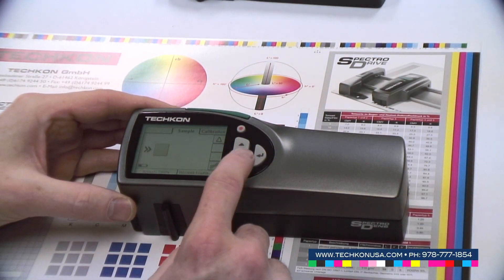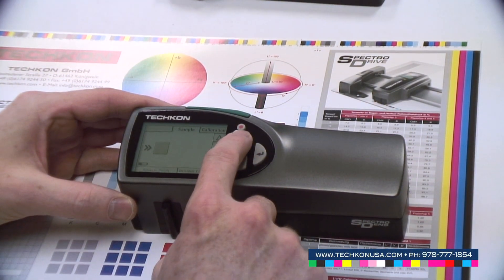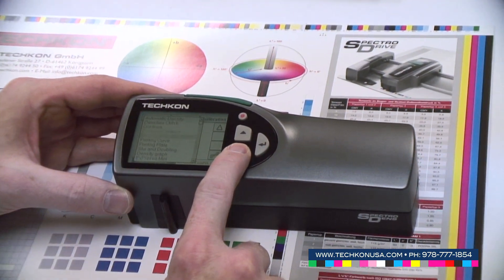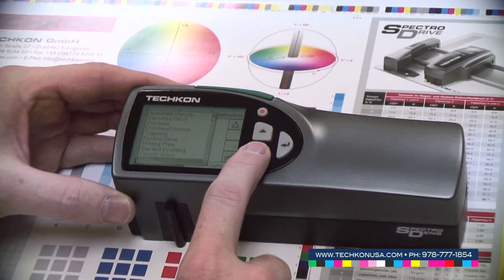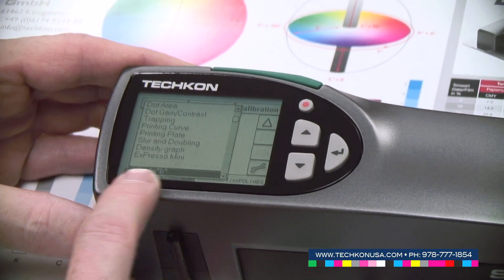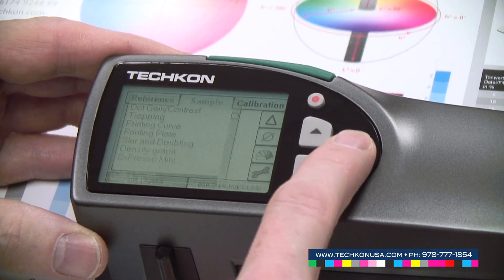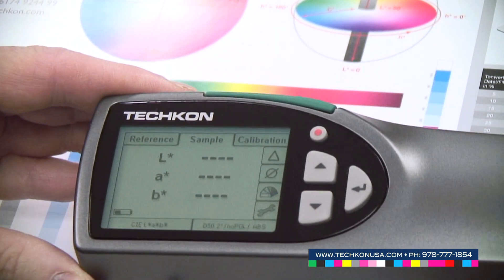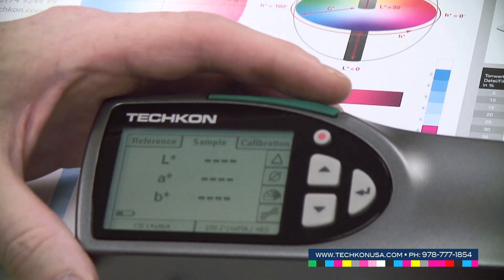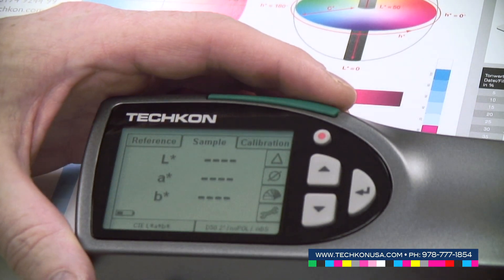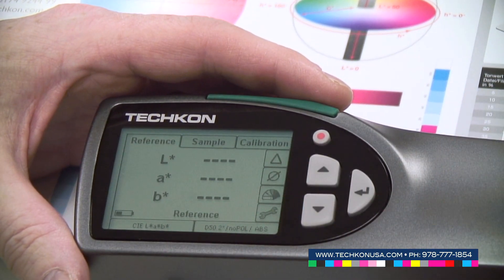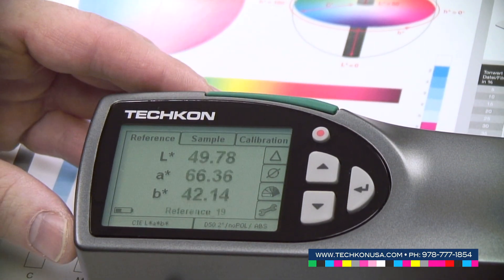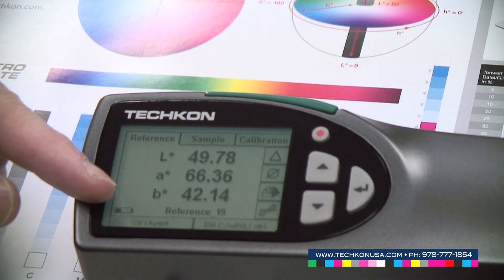Coming to the colorimetric functions of the instrument, which will be indicated by a line in the list, we are going to the CIELAB measurement. Here we can measure our LAB values. I'm using the red patch in the center again as a reference. I have to select reference with the control buttons, measure the red color, and I get my LAB values.